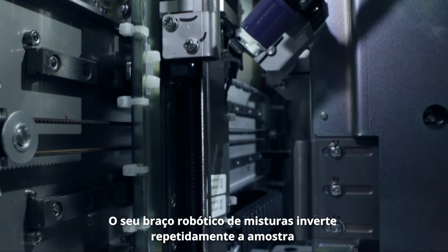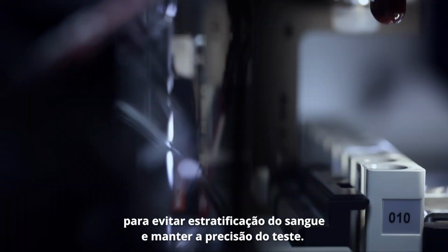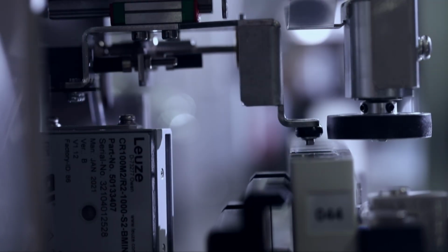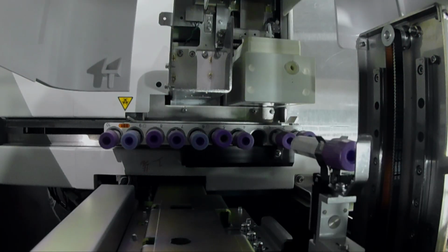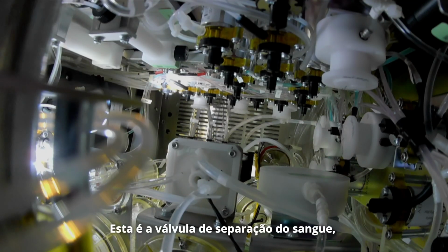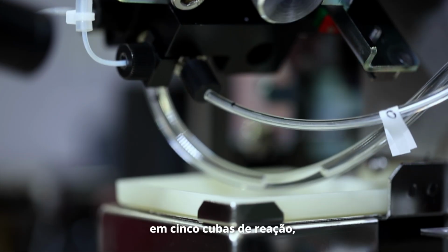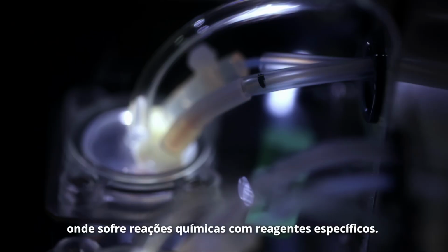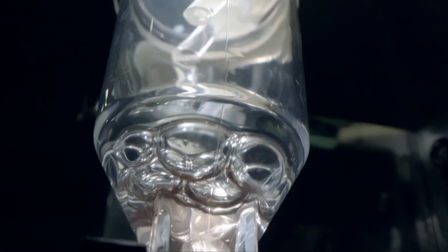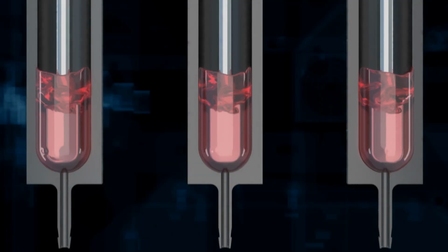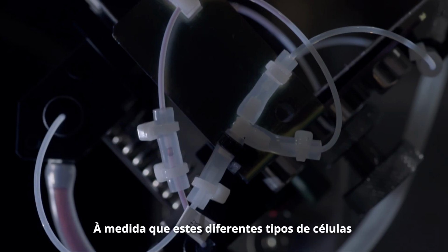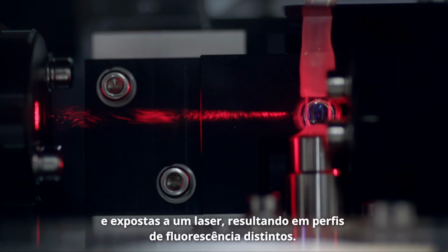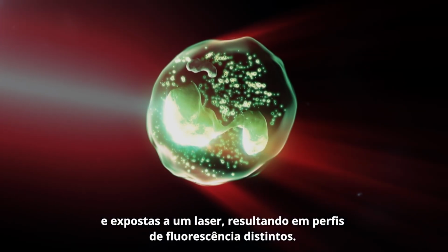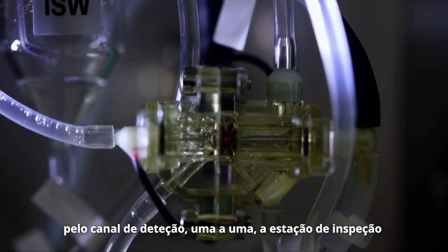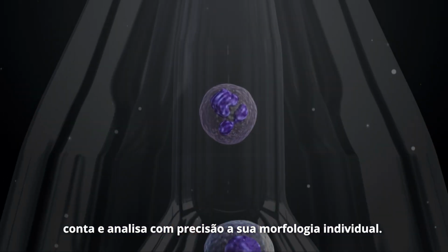The first station is dedicated to completing the blood count. Its robotic mixing arm repetitively reverses the sample to prevent stratification of the blood and maintain test accuracy. This is the blood separation valve, which is responsible for dividing the blood sample into 5 reaction pools, where it undergoes chemical reactions with specific reagents. As these different types of blood cells emerge from the 5 pools, they are stained and exposed to a laser, resulting in distinct displays of fluorescence profiles. When these cells pass through the detection channel one by one, the inspection station accurately counts and analyses their individual morphology.